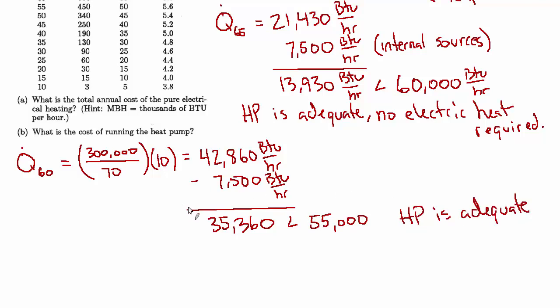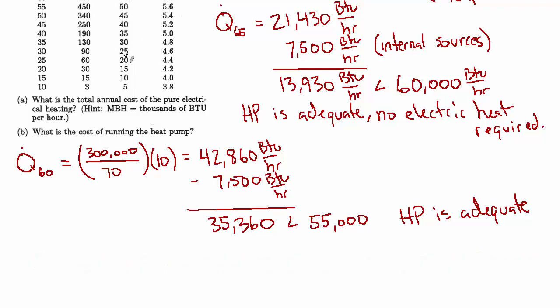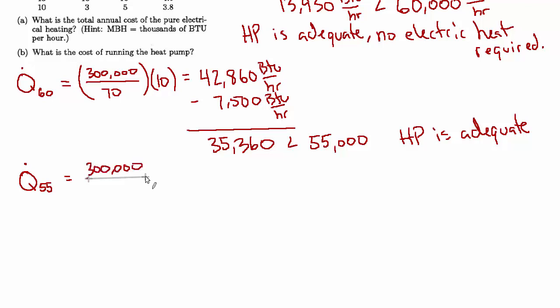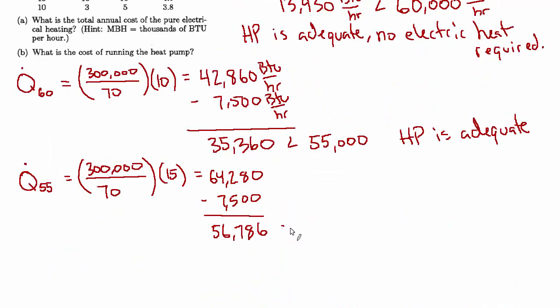Let's do that for the next row as well and see if we need the electric heat. So we'll call this one q_60. Still 300,000 over 70, but now our delta t will be 70 minus 60 instead. So that's only a delta t of 10. And that equals 42,860 BTUs per hour. Again, we subtract the internal load. And the result is 35,360. And the capacity is less than it was before. Now the capacity is only 55 MBH. But that's still more than we need. So the heat pump is still adequate.